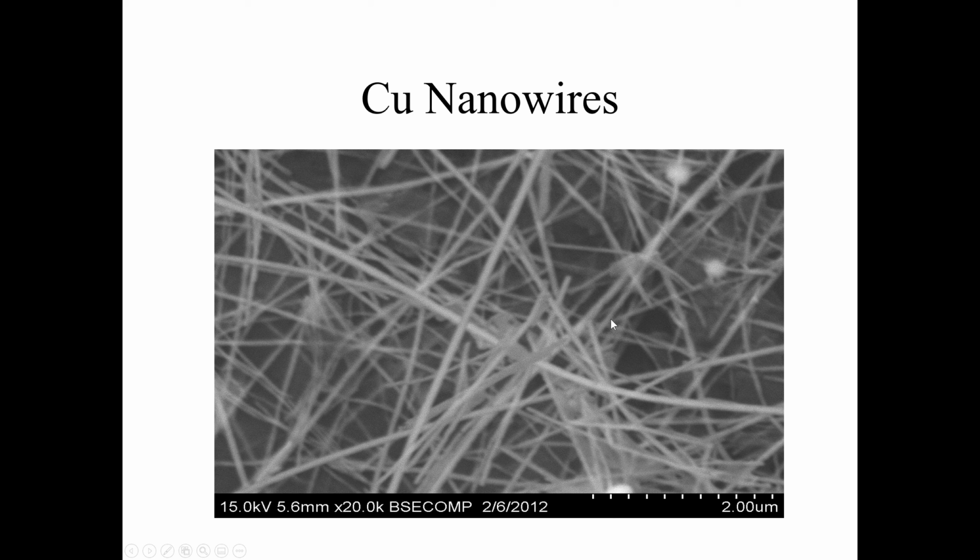The aperture is not perfectly centered. You're using a $100,000 tungsten filament microscope when you should be using a cold field emission gun, which is about a half a mil. So, it's price performance. But again, the researcher can see the fibers, he can measure how thick they are, he can see they're very consistent in structure. Now if I spend a lot of time fine-tuning this or mounting it a little better, I can get it a little sharper.